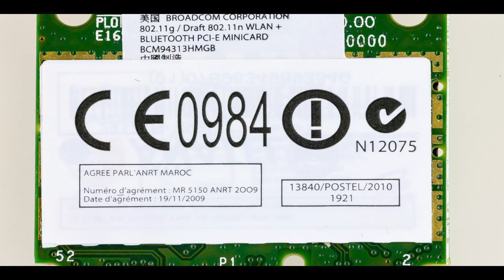A third type of risk control measure consists of providing information for safety to anyone relevant in the manufacturing and use of the device. Think of providing manuals, putting warning labels on the device, and training the people making or using the device. This is the least reliable, but sometimes only way to reduce the risks to an acceptable level. Least reliable because training can be forgotten or put aside in certain situations, warning labels can be ignored or removed, and manuals, well, when did you last read one properly?